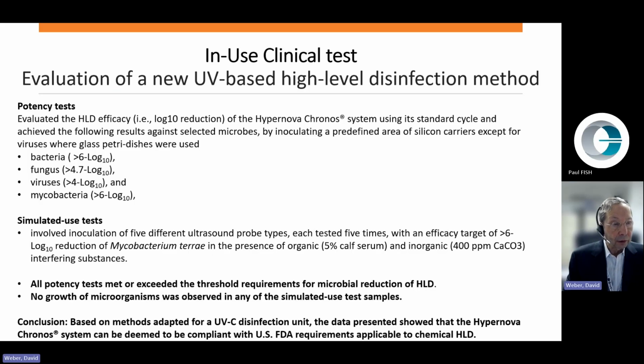This involved inoculation of 5 different ultrasound probe types, each tested 5 times with an efficacy target of greater than 6 log10 reduction of Mycobacterium terrae in the presence of organic, that is 5% calf serum, and inorganic, that is 400 parts per million of calcium carbonate, CaCO3 interfering substances. All potency tests met or exceeded the threshold requirements for microbial reduction of HLD.